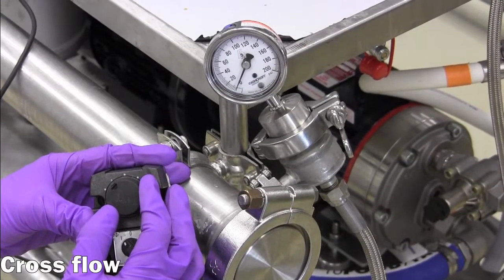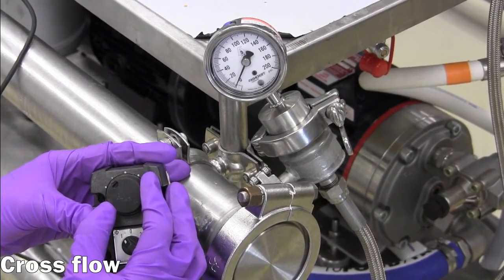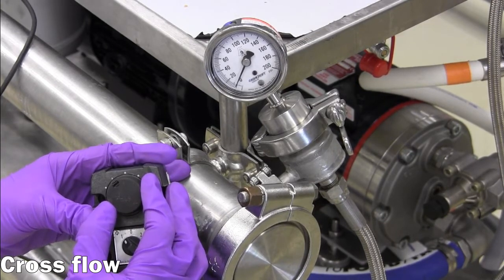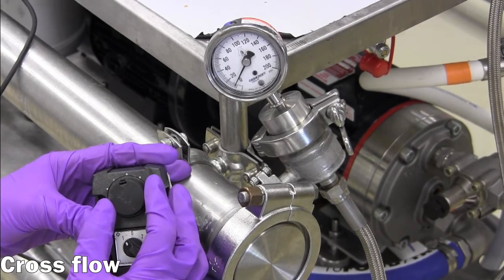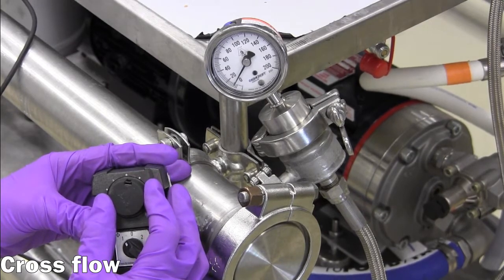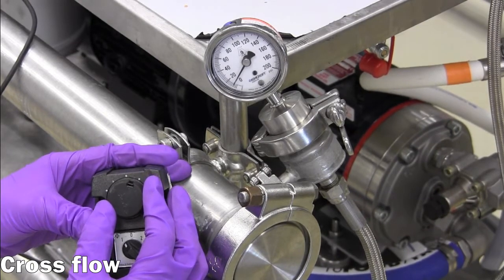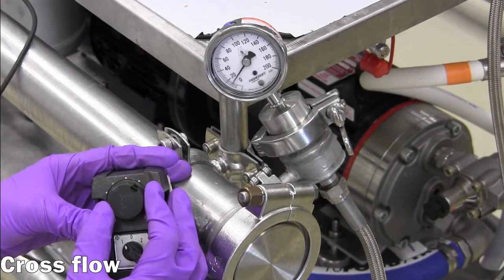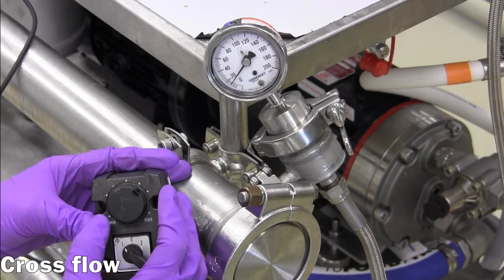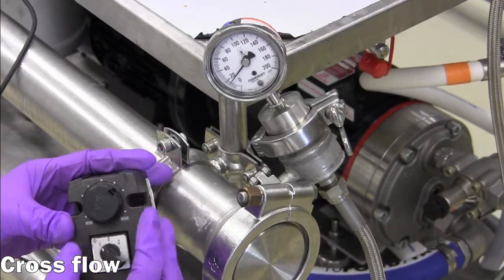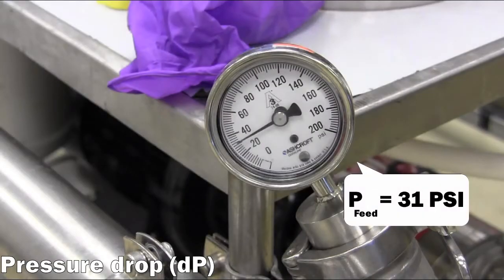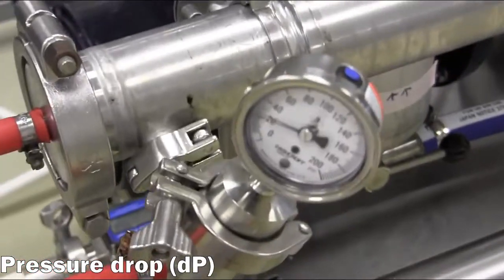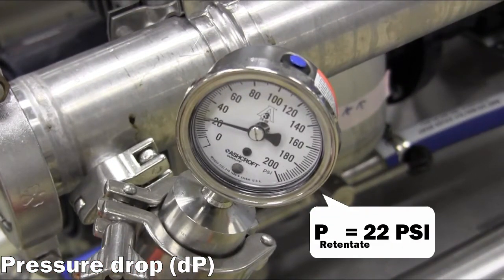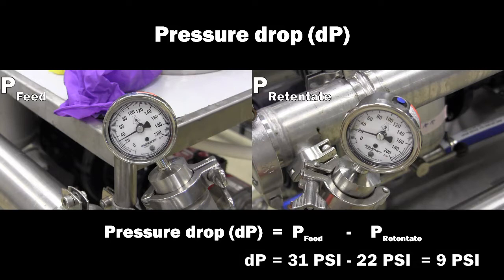The feed crossflow rate is mainly a function of the feed pump speed, which can be adjusted to increase or decrease the crossflow rate. Providing a higher crossflow rate will assist in displacing particulates before they can settle and foul the membrane pores. Increasing the crossflow rate will also increase the inlet pressure on the feed. In this example, the inlet pressure is read at 31 psi gauge and the retentate outlet pressure is read at 22 psi gauge for a total pressure drop of 9 psi.